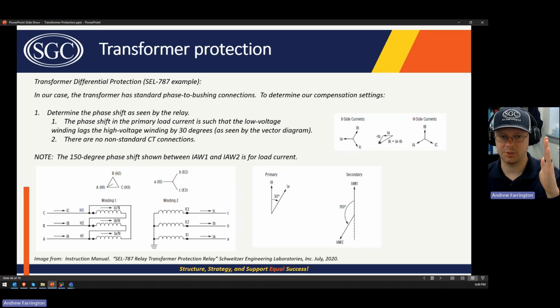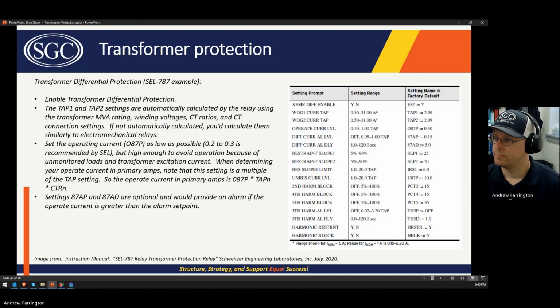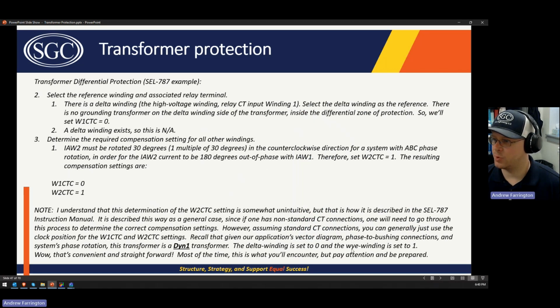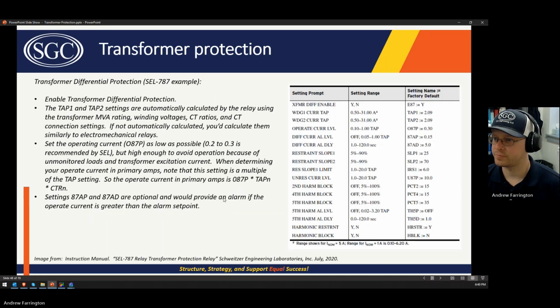I know what my Y winding connection is, and it's a DY11 transformer, so I'll set it to 11, or it's a DY1 transformer, and I'll set it to 1. Okay, and that's what this note is talking about. So read that if my explanation was confusing, and hopefully that will help. Then we get into the other settings that are dependent upon the type of relay you have, okay? Or most of them are dependent upon the type of relay you have.